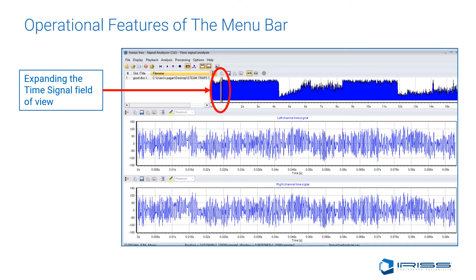Expanding the amount of time viewed in the fields below allows the analyst to go from looking at the entirety of the sound wave to a smaller amount of time. We recommend using only 2 tenths of a second to perform analysis, since harmonic occurrences can be seen repeating several times in this interval. Using the entire length is like looking at the Grand Canyon from 30,000 feet, whereas 2 tenths of a second puts you at 1,000 feet where you can see more of the stratification of the harmonic indications.